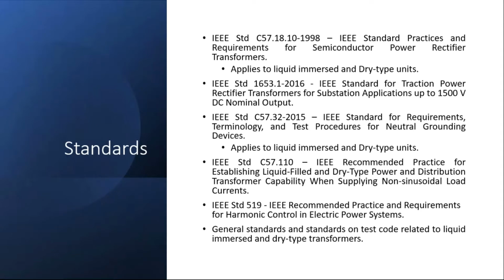Let me invite Bala now to talk about the standards which these transformers are built to and how they bridge the specification between consumer and manufacturer. Okay, thank you, Parminder. We have a few different standards which cover the special transformer requirements, starting with IEEE standard C57.18.10. This standard is for semiconductor power rectifier transformers, which include both single phase and three phase, and both liquid and dry type.